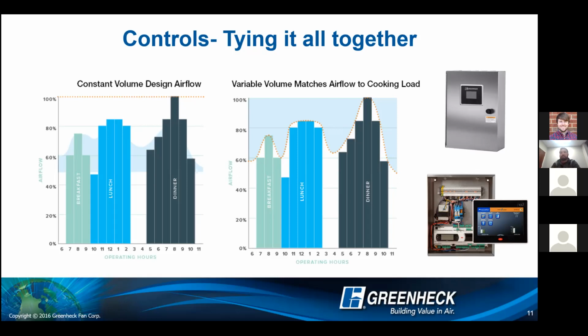Because in that school setting or in a bakery setting, somewhere where you don't have a lot of variance in your heat, you also typically don't have high heat. You're using ovens, you have some pretty low heating capabilities of those appliances. So if you were to utilize a variable volume system and have the slightly higher upfront cost, the long-term savings on that system would allow for the system to be truly running at 50, 60, 70% of design for the rest of the system's life, which is going to be a cost savings long-term on the system.